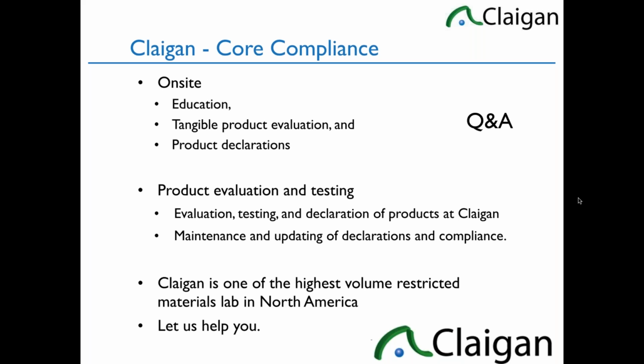And so we do MDR quite a bit. You have to be somewhat strategic. There are other parts of the MDR that are very complicated. The allergen component is a bit open-ended. We restrict it right now to nickel and latex until more is known. So one thing we know is any chemical can be made into an allergen, and that makes life difficult. So we have to stay with known ones, and that's actually even harder than the CMR.